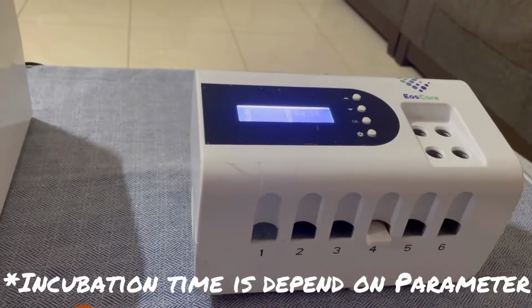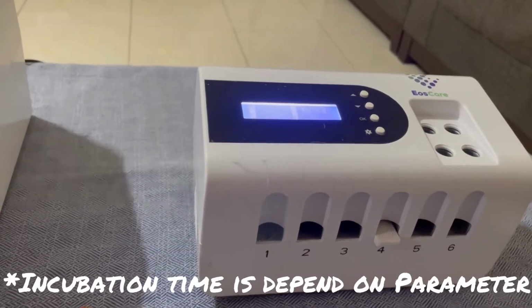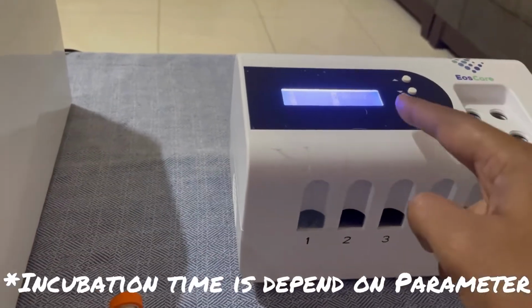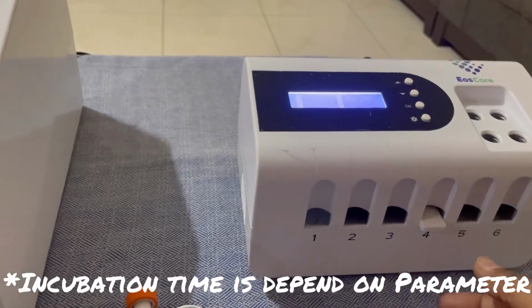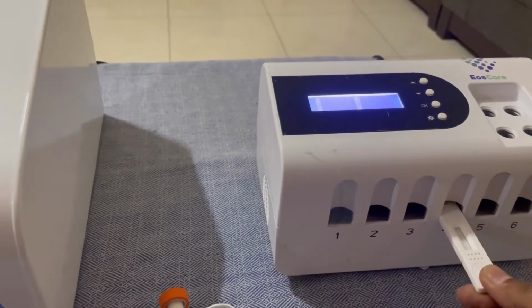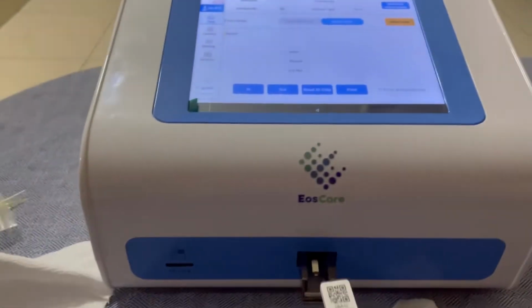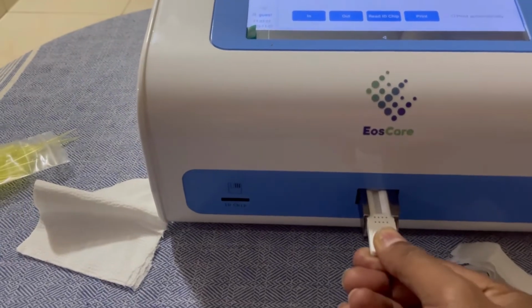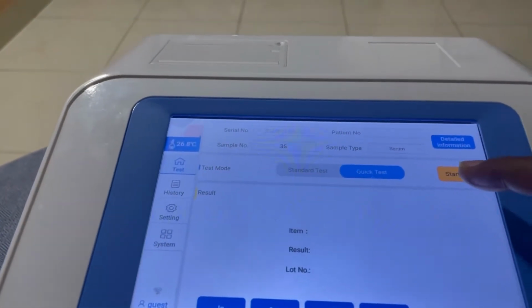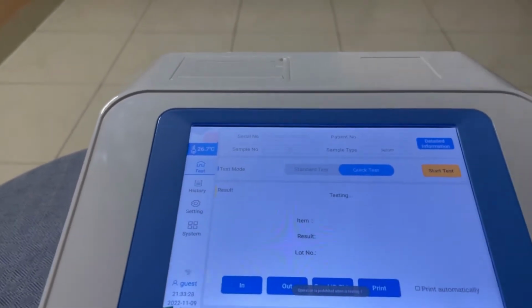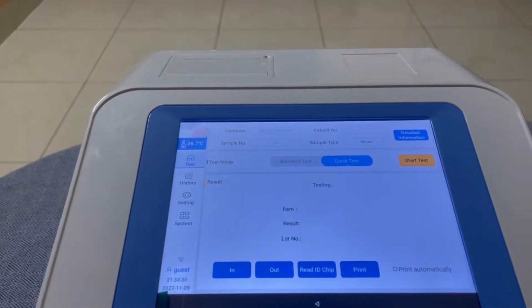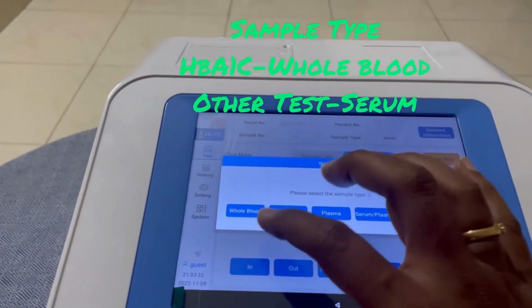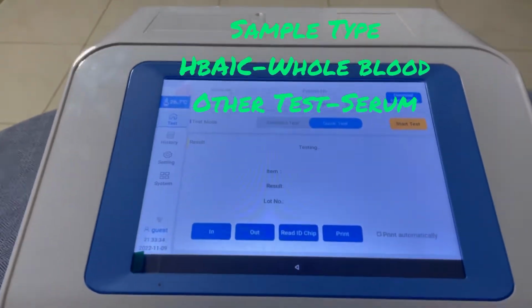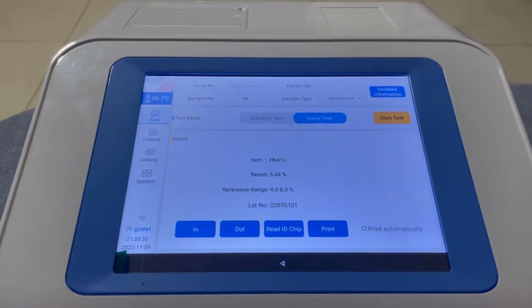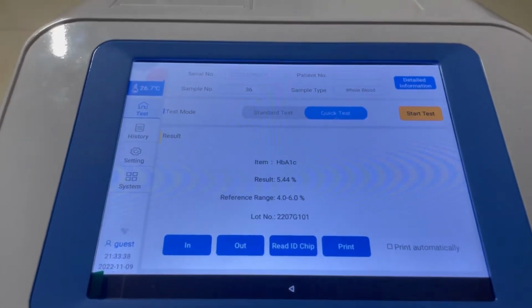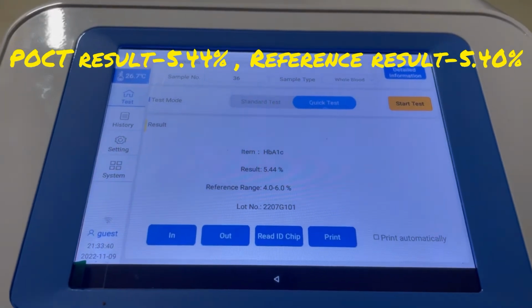Now the 5 minute incubation is about to complete. Once 5 minutes are completed, it will give a beep as well as blink. So I am removing it and now I am going to take the reading. I will click start test. The first time it will ask what the sample type is, so I have to select whole blood for HbA1c. You will get the result. As you can see, the result is 5.44.